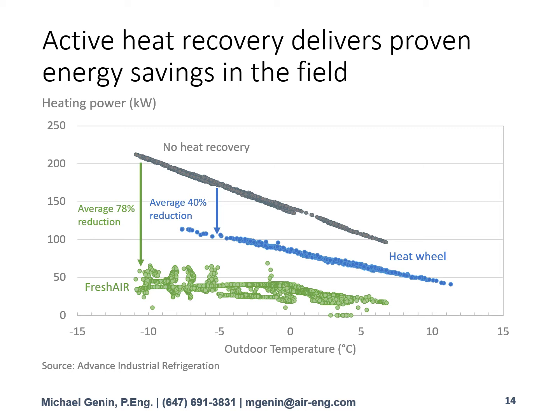And you might immediately ask, why is the correlation a little scattered in some areas? Well, the FreshAIR unit operates like any refrigeration device with multiple circuits and multiple compressors, and occasionally you have compressor cycling and compressor rotation, where one of the compressors turns on and that heat is not immediately realized in the supply air stream. You have small moments, and when the data logger picks that up, you get those small outliers. But it is a substantial reduction in energy, and if we look back at the theoretical model from before, where FreshAIR had a projected operating cost of $13,000, and we compare it with the straight up electric heat, this reduction of 78% is almost dead on with the theoretical amount of energy reduction.